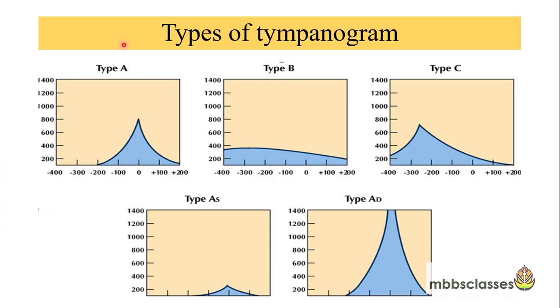When a report is produced, tympanograms are classified into types: Type A, Type B, and Type C. Type A has two variations — Type AS and Type AD. Type A is a normal tympanogram; Type B is a flatter curve; Type C shows compliance peak shifted toward negative pressure; Type AS has normal pressure but low compliance; and Type AD has compliance exceeding the equipment's upper limit.